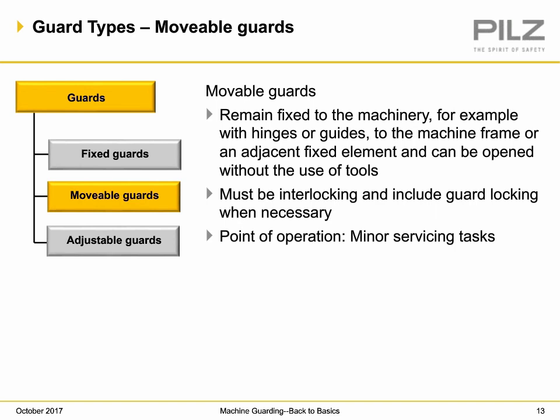Minor servicing tasks, as outlined in the OSHA standard, but also if you are familiar with or have a copy of the ANSI Z244.1 standard, talks about minor servicing tasks. They are routine, they are repetitive, and they're part of production. So I have an interlocking system that's effective. It doesn't say it has to be a Category 3 or a Category 1. Your risk assessment will make that determination of what level of safety circuitry integrity you will need for your interlocking systems to be able to perform minor servicing tasks.